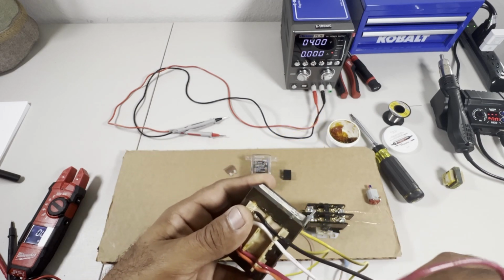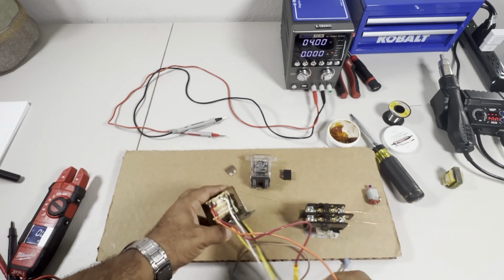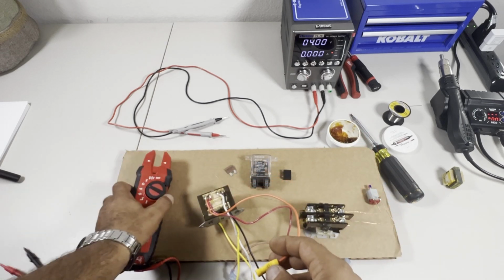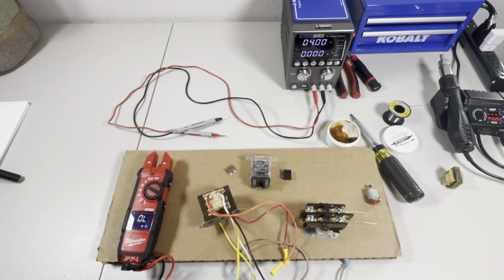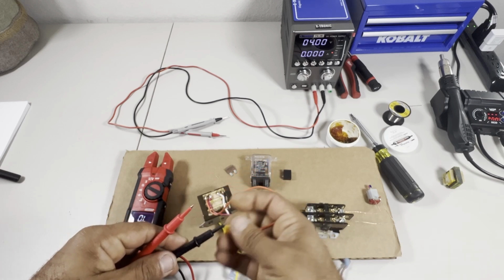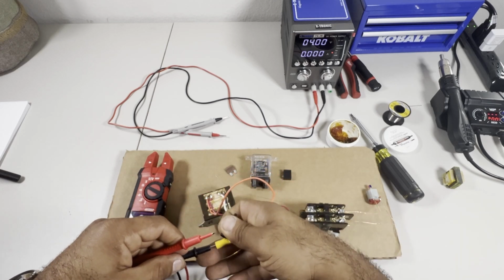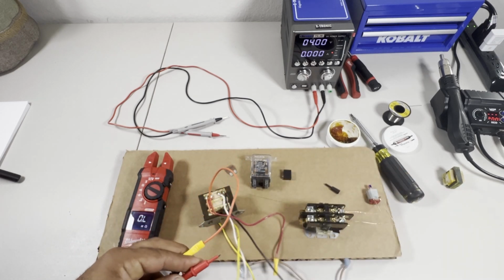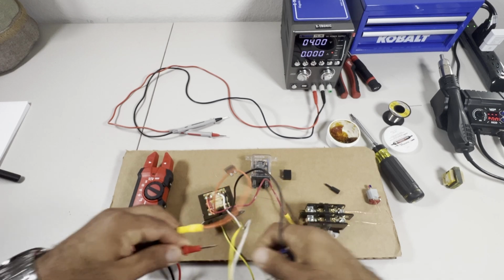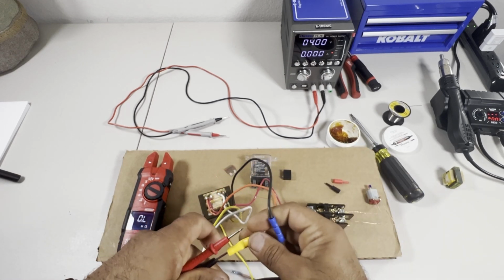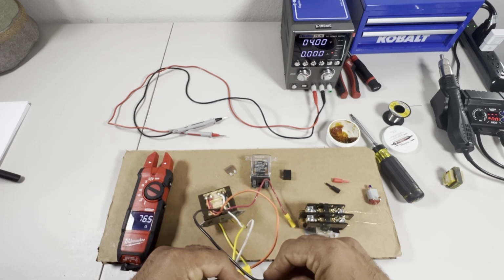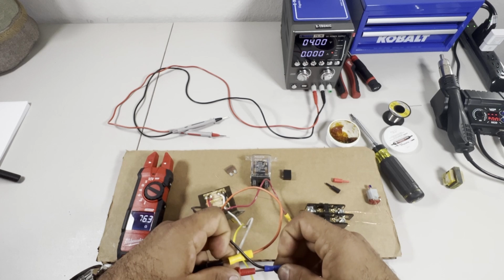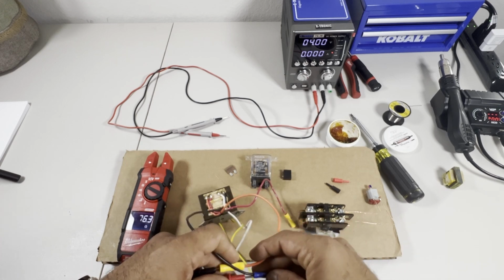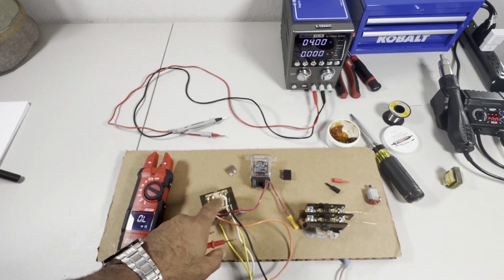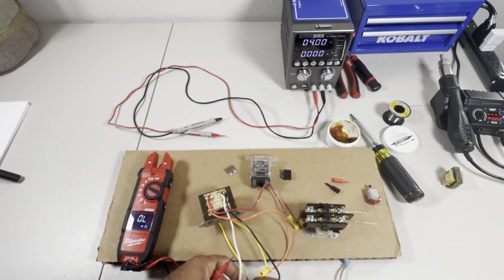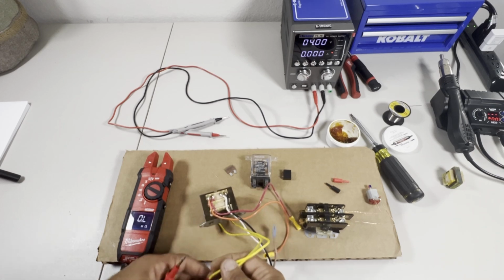So between the first wire, which is your common black, and the last wire, which is the orange, that's the beginning and the end of your loop. If you want to check this transformer to see if it's good or bad, you're going to put your ohm meter on the ohm reading, and one wire to the orange one. You have to make sure there is no power to that circuit first. That's very important. You're going to check between orange and black. Let's see if we can get that ohm reading. There we go. We have 76.4 ohms. If you don't get that reading between the first and the last wire in the circuit, that means the wiring inside is burned out, is open.